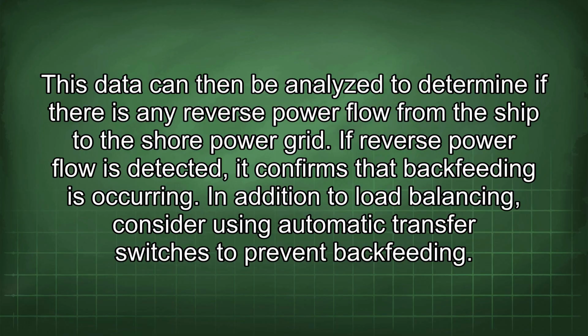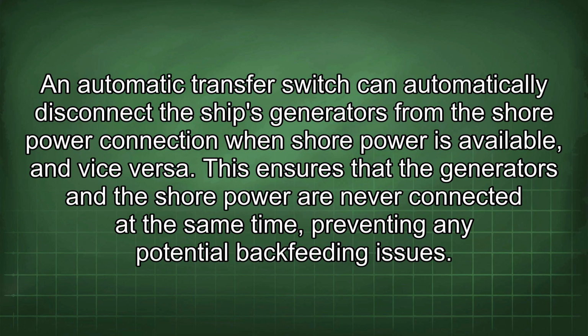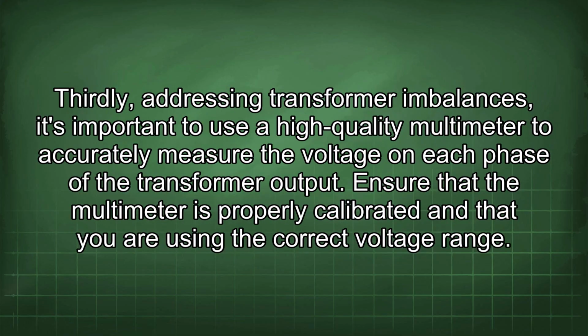In addition to load balancing, consider using automatic transfer switches to prevent backfeeding. An automatic transfer switch can automatically disconnect the ship's generators from the shore power connection when shore power is available, and vice versa. This ensures that the generators and the shore power are never connected at the same time, preventing any potential backfeeding issues. Thirdly, addressing transformer imbalances.